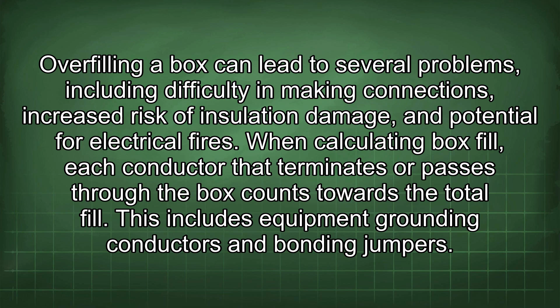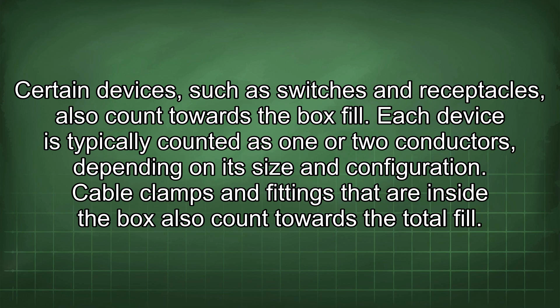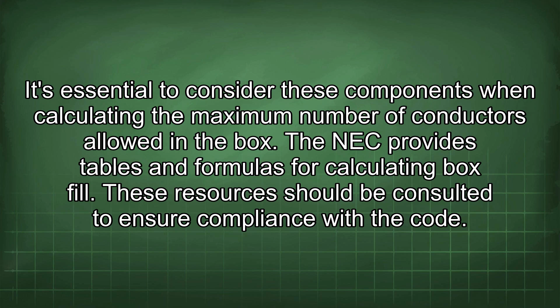Each device is typically counted as one or two conductors, depending on its size and configuration. Cable clamps and fittings inside the box also count toward the total fill. It's essential to consider these components when calculating the maximum number of conductors allowed in the box. The NEC provides tables and formulas for calculating box fill.